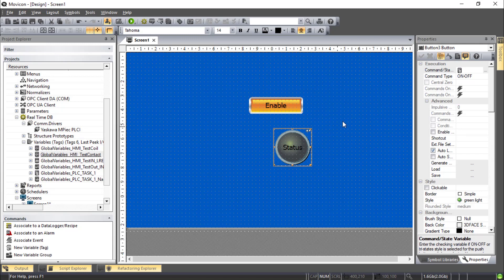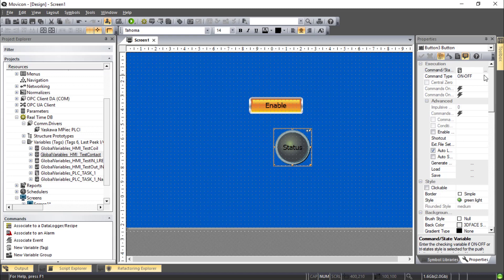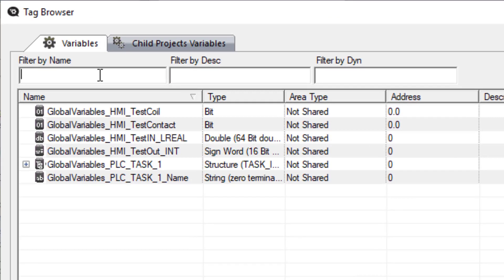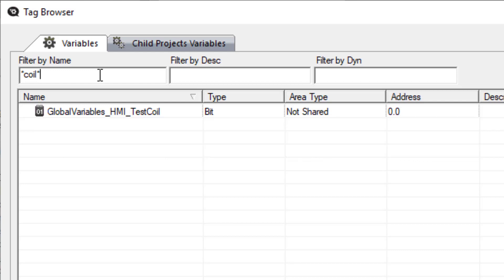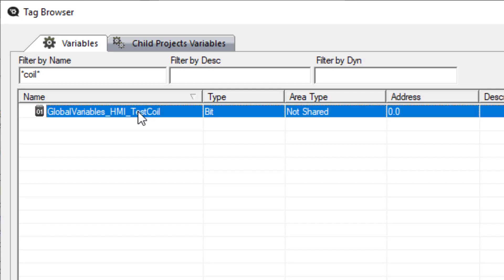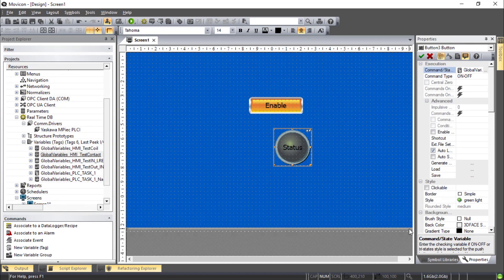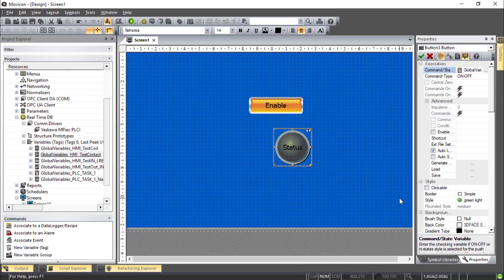And I could drag the test coil onto status. But there's another way that you should know how to do and that is to look at the properties on the right hand side for that object. And go to Command State Variable and click the ellipsis. This brings up the tag browser. It's pretty easy to filter a long list by using wildcard characters like the asterisk. And find the variable that you want. There's Test Coil OK. The result is the same.